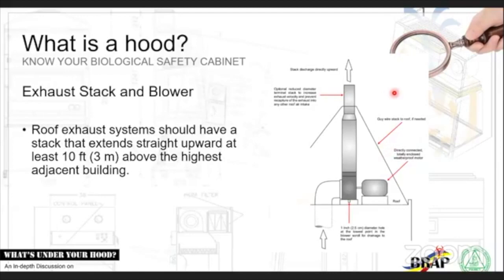Okay, so we'll be talking about ducting and everything. This is an example of your ducting outside. So all ductings have what you call dampers. Those dampers control the air velocity, or how much air actually passes through your pipes or your stack or your ducting. Okay. So if you're going to place the ducting, you need to have a clearance of 10 feet or 3 meters above the highest adjacent building. So if you have two structures standing beside each other and you happen to be the lower one, you need to place your ducting 10 feet above the next one. Because if it's lower than the adjacent building, imagine where all your exhaust air goes to.